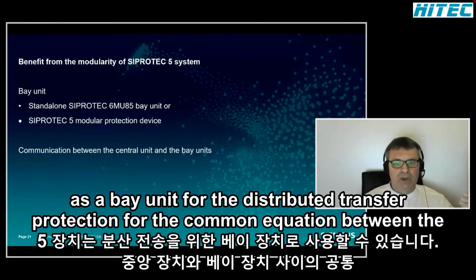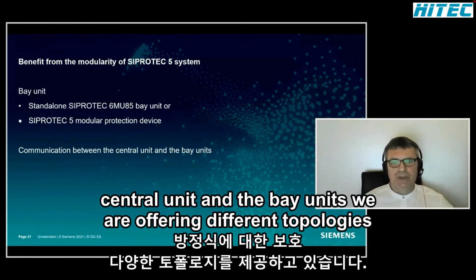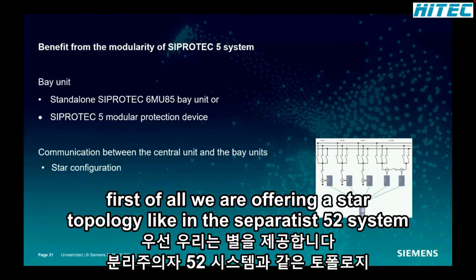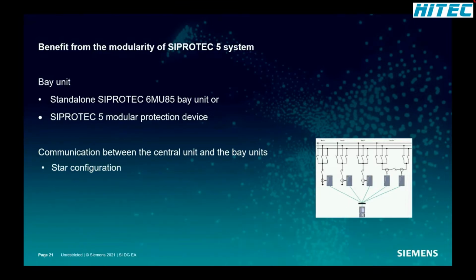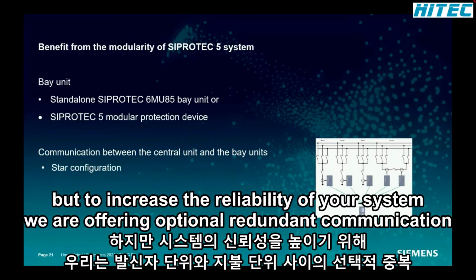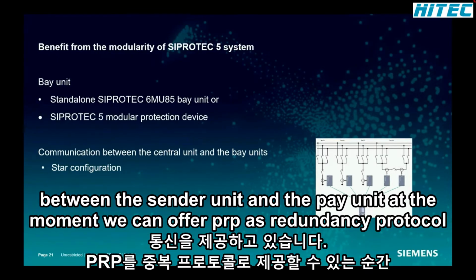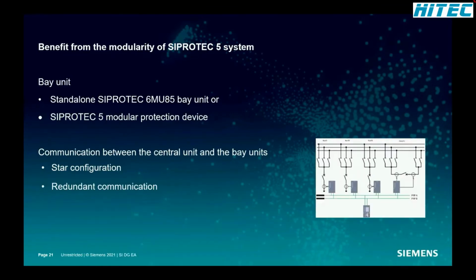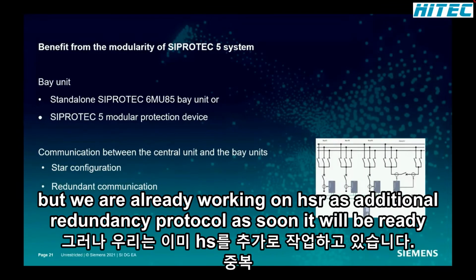For the communication between the central unit and the bay units, we are offering different topologies. First of all, we are offering a star topology like in the 7SS52 system. But to increase the reliability of your system, we are offering optional redundant communication between the central unit and the bay unit. At the moment, we can offer PRP as redundancy protocol. But we are already working on HSR as an additional redundancy protocol.